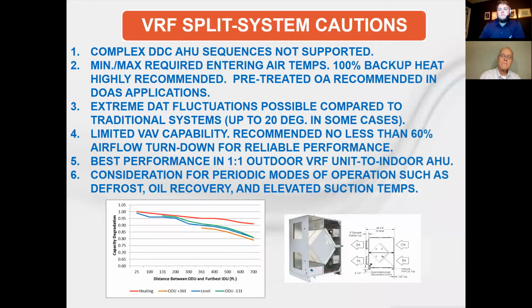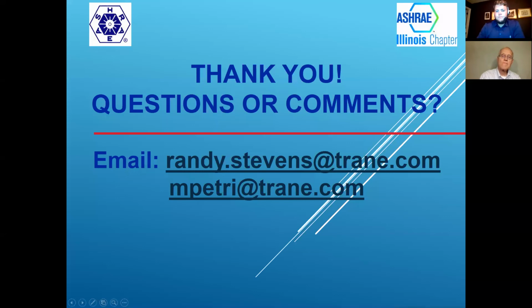Do we have any final last questions? Anyone that's on? Looks like VRF has freon in occupied spaces. In case of fire, a pipe joint melts, and freon enters the room and burns. Is this considered? You say that again, Mitch? VRF having refrigerant in the occupied spaces, in cases of fire, a pipe joint melts, and freon enters the room and has a flammability issue. Is this considered in design right now?